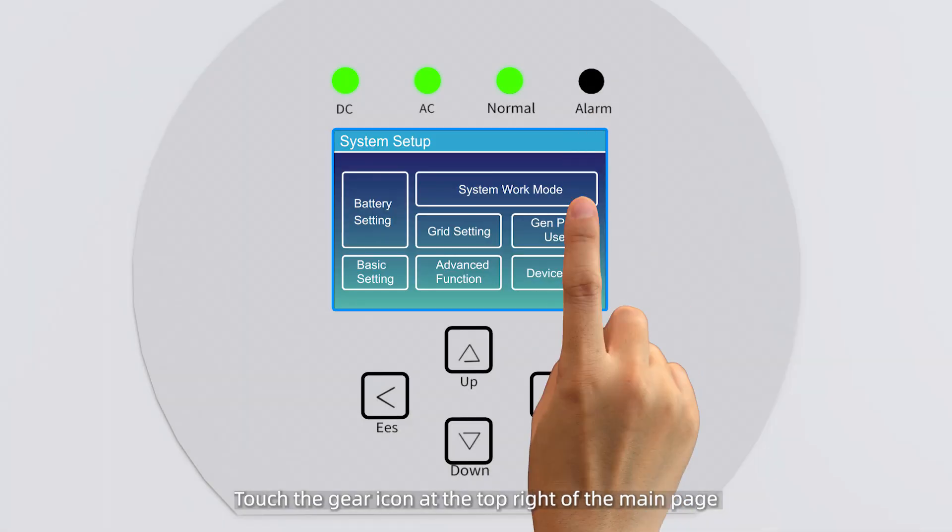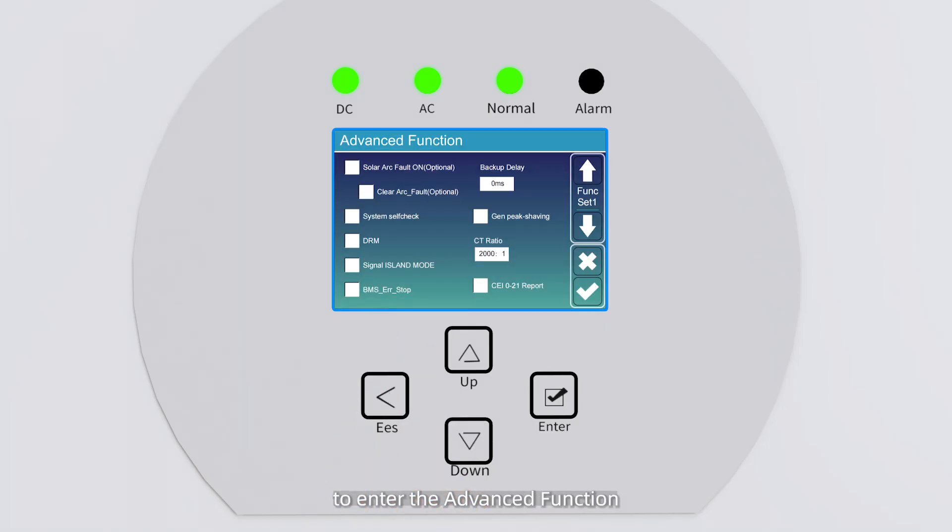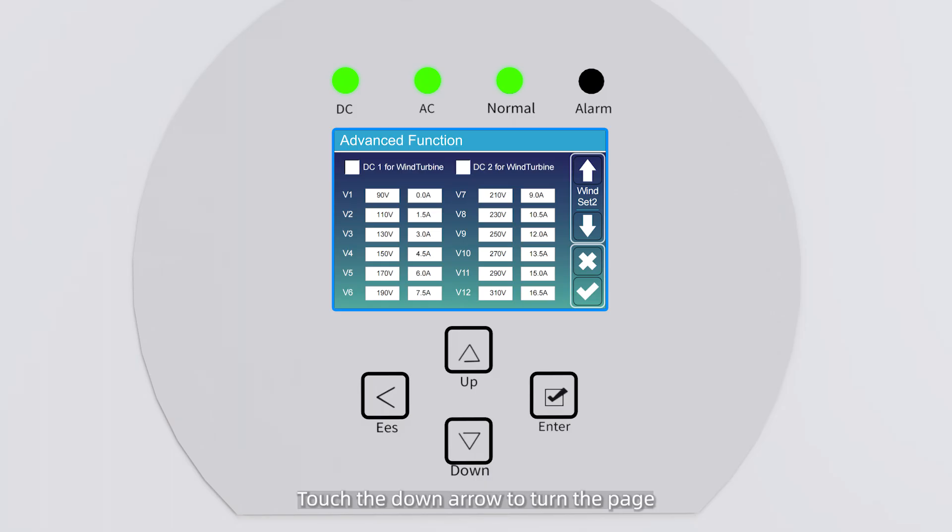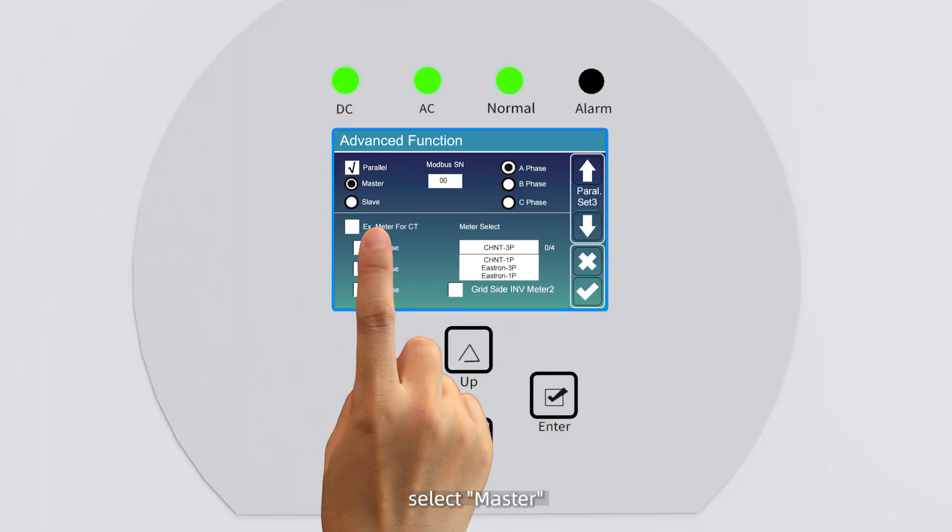Touch the gear icon on the top right of the main page to enter the advanced function. Touch the down arrow to turn the page. Check the parallel mode. Select Master and set Modbus SN01 to 16 to adjust the Modbus communication address of the master inverter.